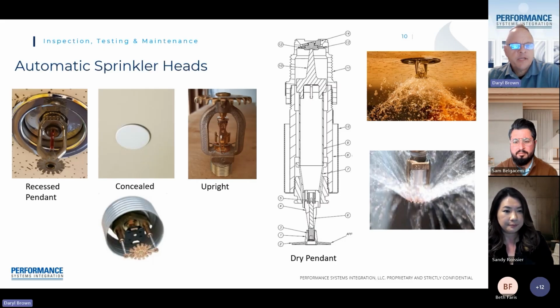Basically, these are a few other pictures of fire sprinkler heads and what they look like and how they are positioned. On the left is a pendant. On the right is an upright. As you can see, there are different styles of links on each one of them. The link is what operationally activates the sprinkler head to actually discharge water. The piping is pressurized at all times with water. The only thing that prevents that water from discharging at any one time is, on the left-hand side, that red bulb. On the right, you see a metal link.